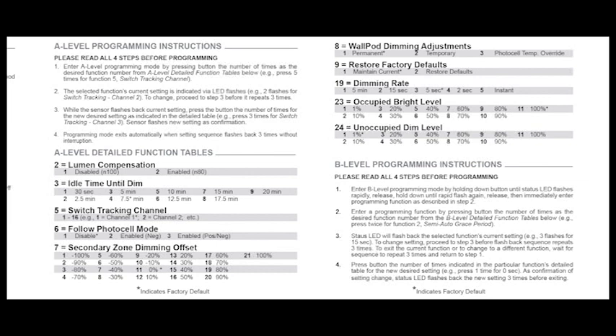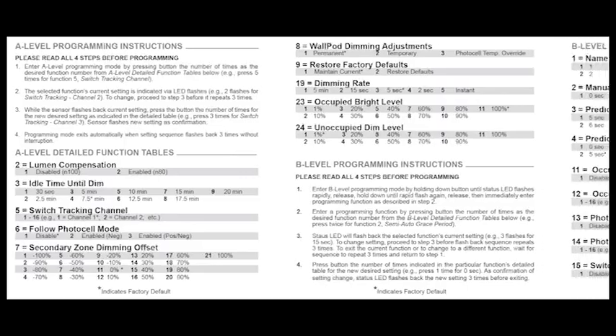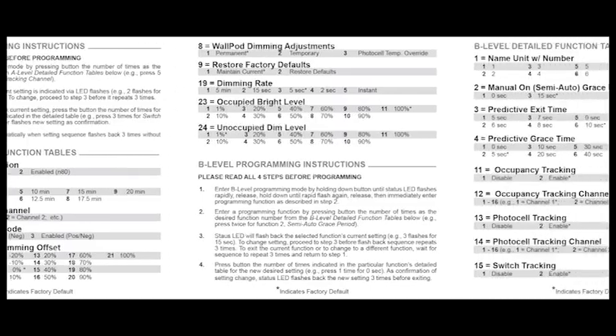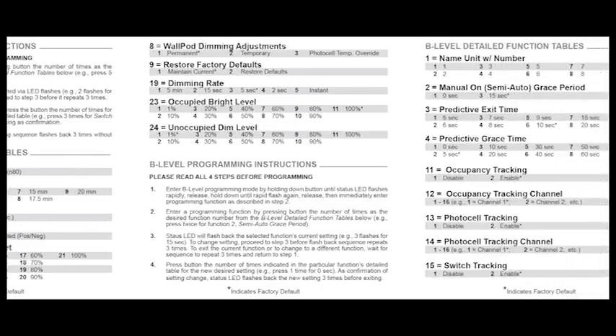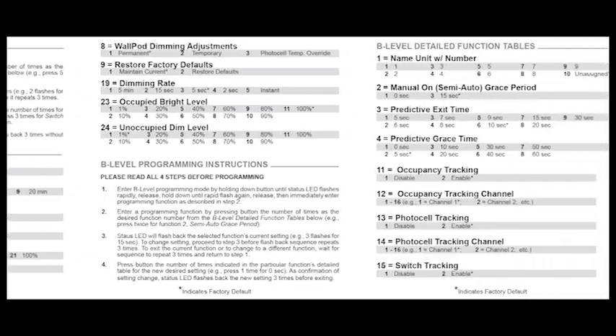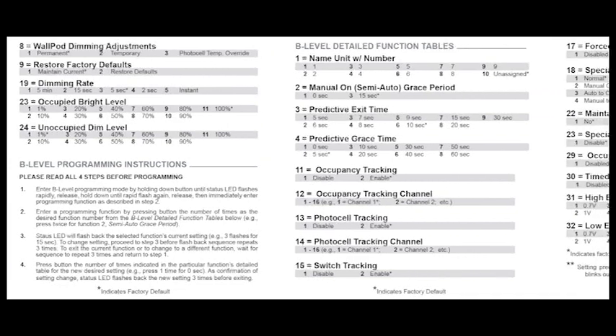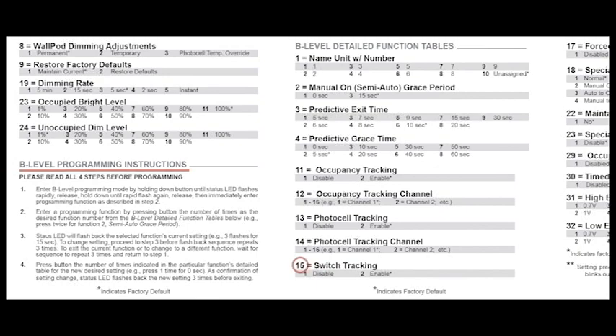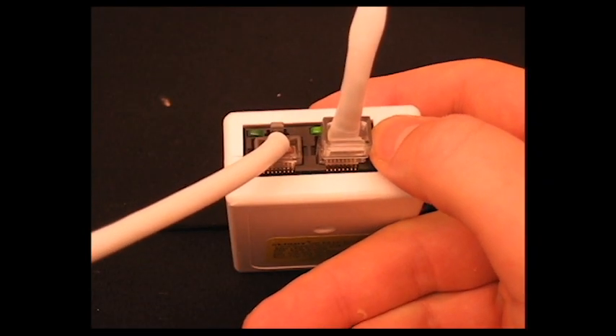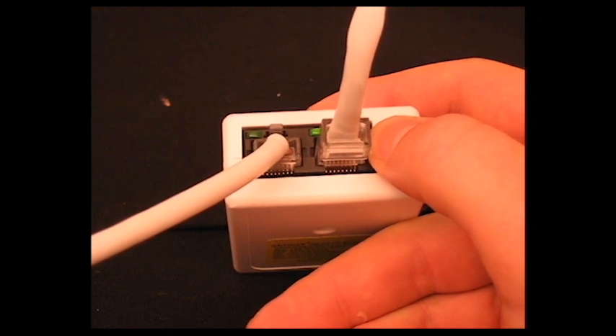For another quick example, let's change our switch tracking, which will indicate whether a luminaire will react to the device. Switch tracking is housed under the B level programming and refers to number 15 in our detailed function tables. To enter B level programming, hold down the programming button until the LED flashes multiple times, release, and then repeat a second time.